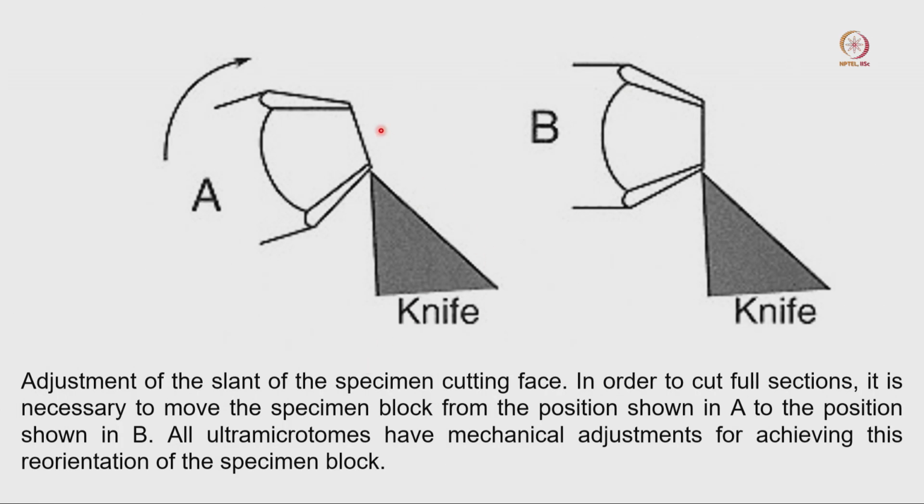Okay, there are a couple more suggestions. If your sample is tilted like that and your knife or blade is going to do a section, most of the time with this kind of blade position, and if your tissue sample is located like that, it is going to break the entire tissue, because it cannot apply the force properly, or sometimes it will break or damage the tissue. Only a small part will come out from that tissue. So, always your tissue sample should be located like this and your knife should be parallel with this one, so you can get the proper section of that particular tissue.